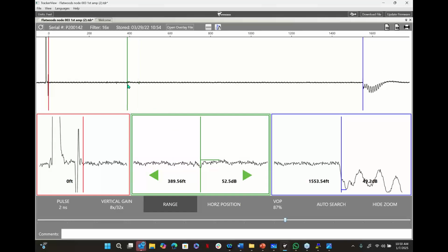I see this event over here at about 389. I see another one at 338, and I see another one over here, possibly. I said, okay, so tell me this. What's your next move? He said, well, now that I see that, I want to get out there in my bucket truck, start to feel around, see if I can find something out. I said, bet. Call me as soon as you find out, which he did not, but that's neither here nor there.